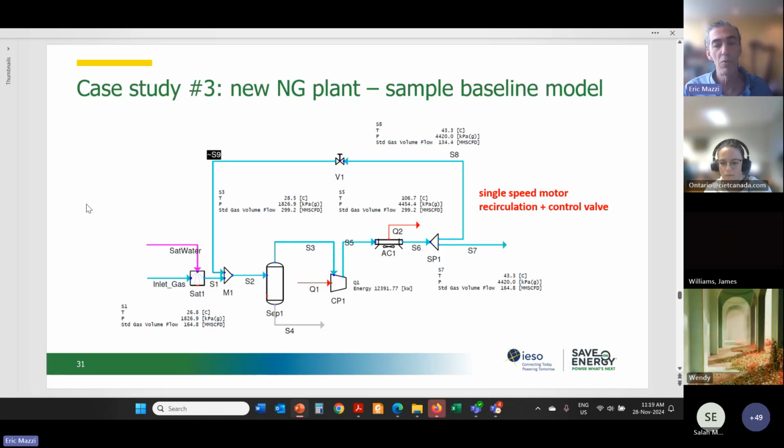Salah, you're referring to that effectively, to say what if we just turn off the VFD and simulate how they would have to do valve control and recirculation. Well, we haven't found any operation able or willing to do that. But that is definitely a valid and common M&V method. So good point. Josh, I see your hand up.